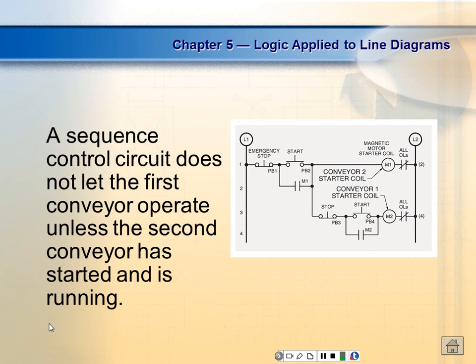By the way, when you're wiring these circuits, if it don't show the wiring diagram for the power circuit, don't hook the motor up. There's one circuit that we have that it's a sequence starter, but it runs 2 motors. We've had this happen several times, but they don't do the wiring right, and 2 motors start at the same time. It blows the fuses and are disconnected.